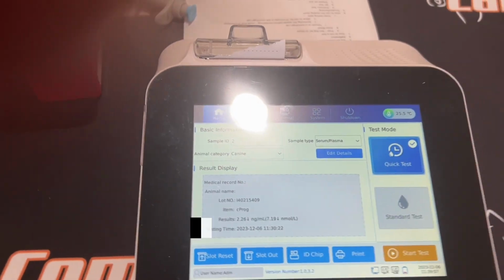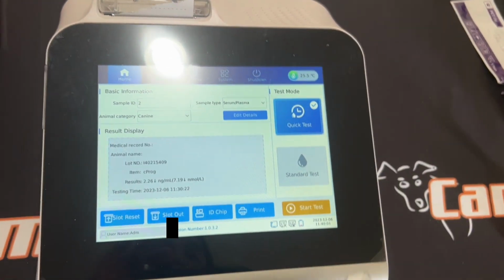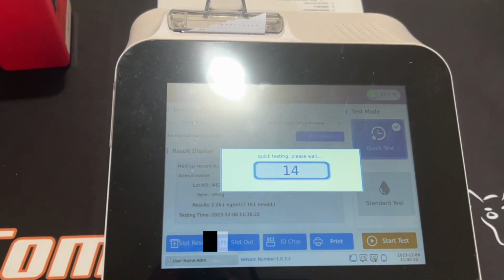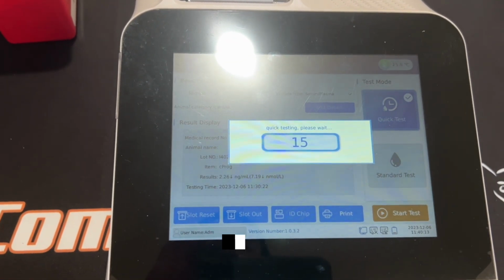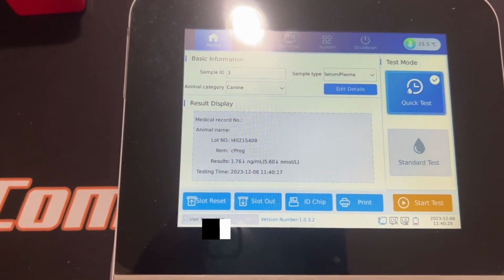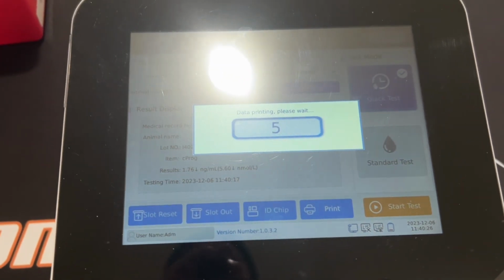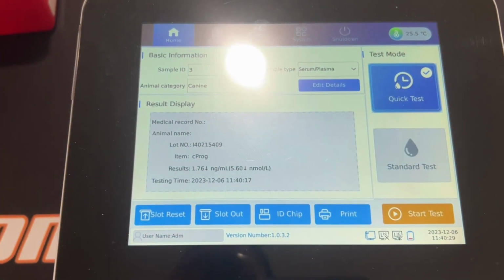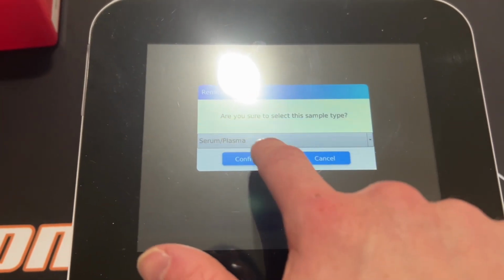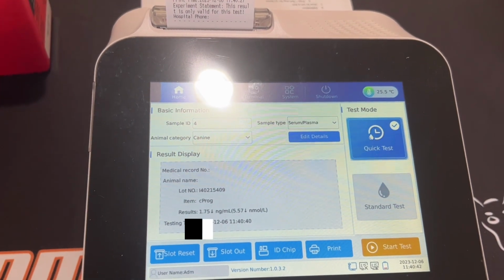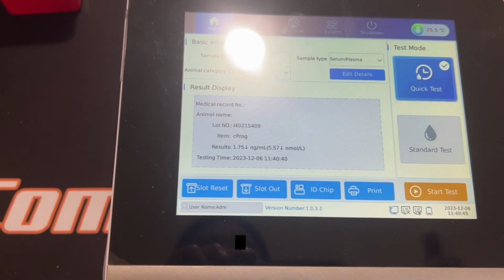So what we're going to do is click on Quick Test, take an old used test cartridge, the one that we just used will work fine, and place it in the machine, and all you're going to do is run it 5 times in a row on Quick Test. Confirm. We get a 1.76, we'll print that. We're going to run it one more time. We're going to run it a total of 5 times. 1.75.